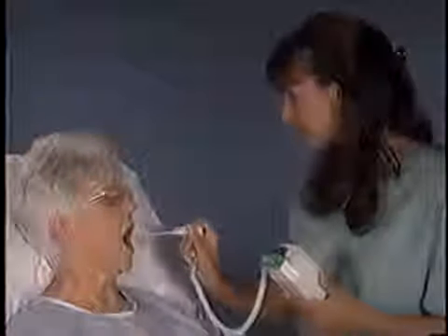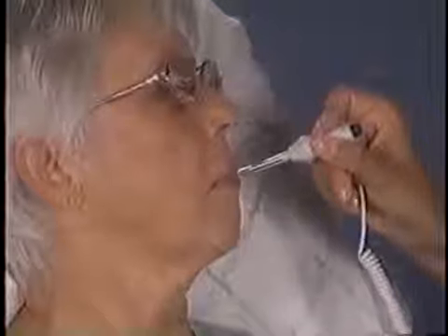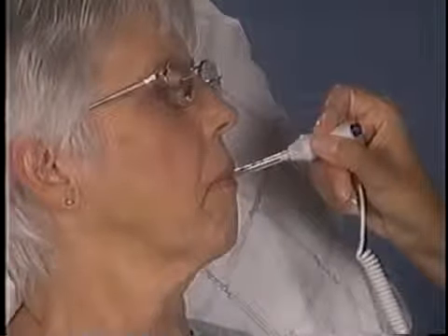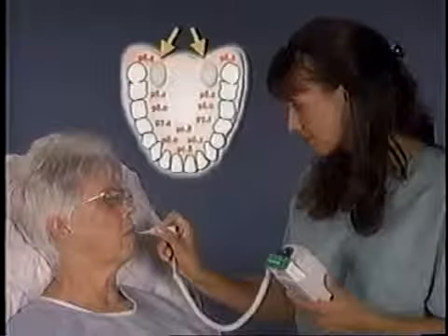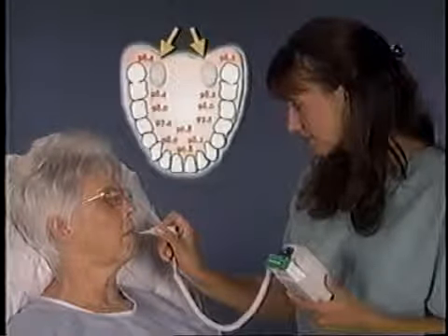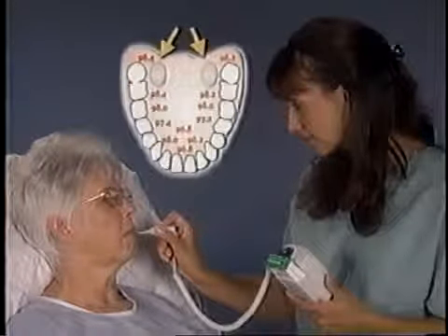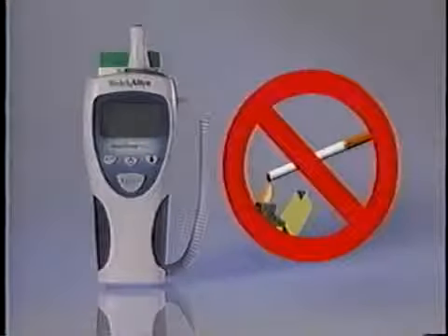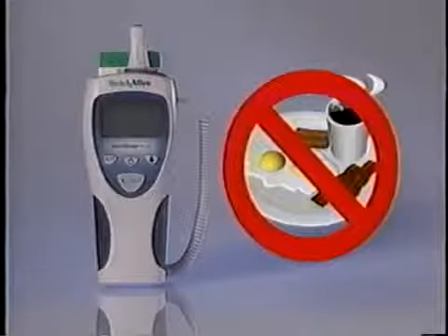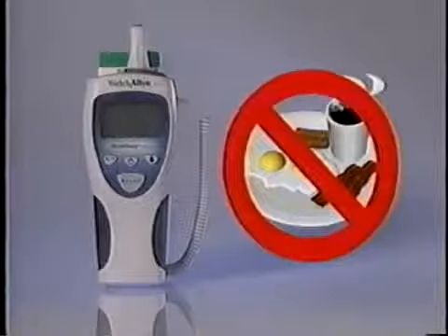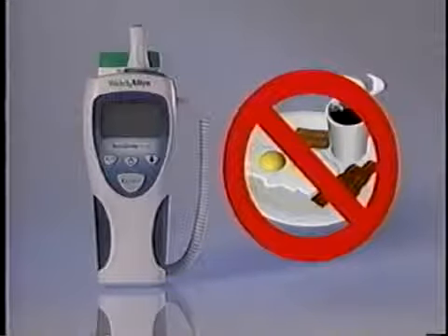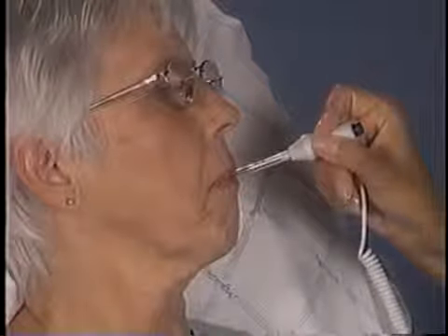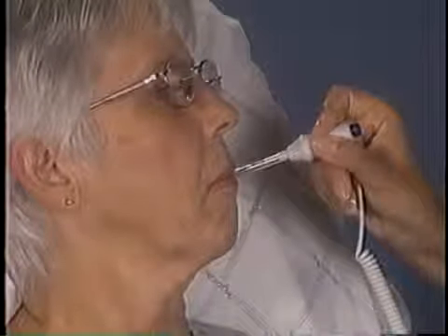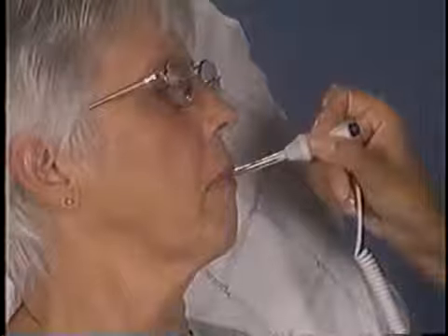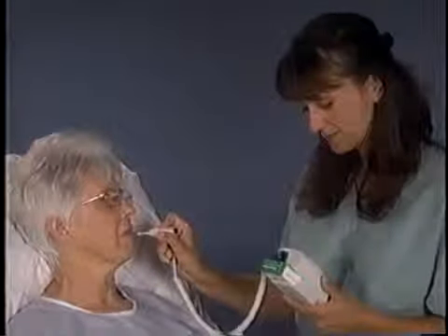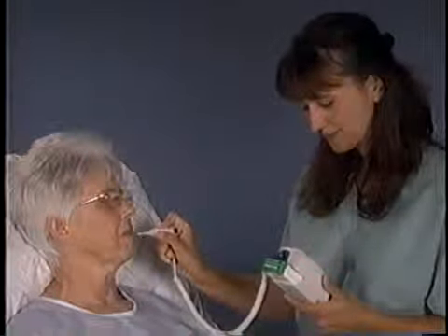Place the probe under the patient's tongue on either side of the mouth in the rear sublingual pocket and have the patient close their lips around it. Measurements outside the sublingual pockets will result in lower readings. To get the most accurate reading, the patient should not smoke, eat or drink hot or cold food or beverages for at least 20 minutes before taking their temperature. Hold the probe in place, keeping the tip of the probe in contact with the oral tissue during the entire measurement process. Urge the patient to avoid breathing through the mouth or speaking.